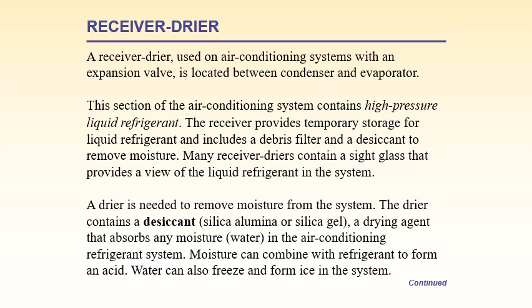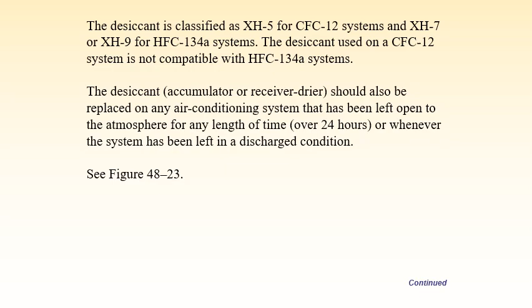Now next important thing is the desiccant. The desiccant is classified as XH-5 for CFC-12 and XH-7 or XH-9 for HFC-134a. Desiccant used on a CFC-12 system is not compatible with that of an HFC-134a system. The desiccant should also be replaced on any air conditioning system that has been left open to the atmosphere for any length of time over 24 hours, or whenever the system has been left in a discharged condition. So we have to replace this desiccant when we have opened this system for a very long time and it is open to the atmosphere.